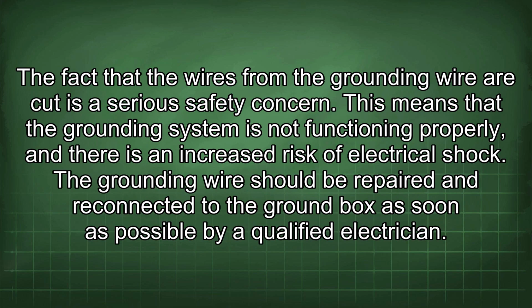The fact that the wires from the grounding wire are cut is a serious safety concern. This means that the grounding system is not functioning properly and there is an increased risk of electrical shock. The grounding wire should be repaired and reconnected to a ground box as soon as possible by a qualified electrician.